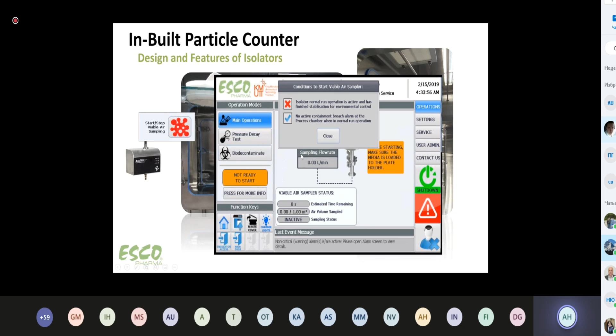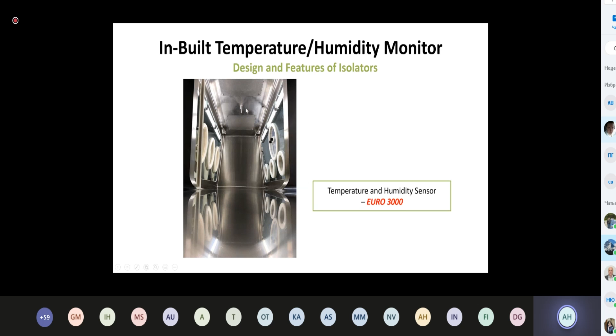This will be some test report, how we check the particle count reading. Remember, we need to achieve grade A, ISO class 5 grade A. So this will be the results and the passing criteria for each particle size. Here will be a monitor of temperature and humidity. This is actually not a control, it's a monitor. And here would be the price, about 3,000 euro.